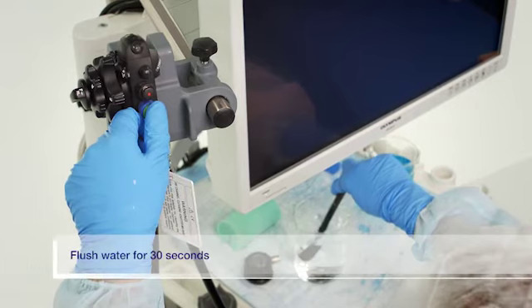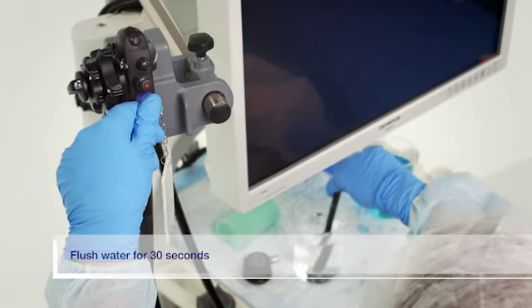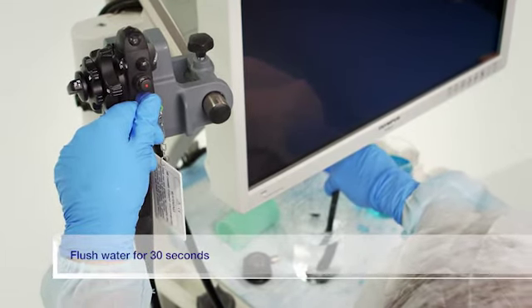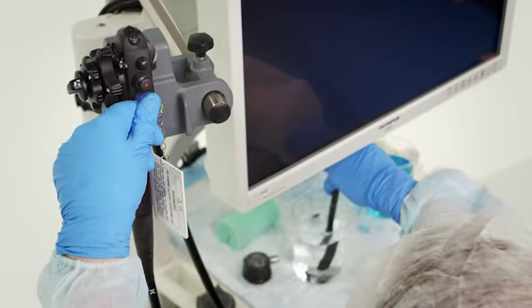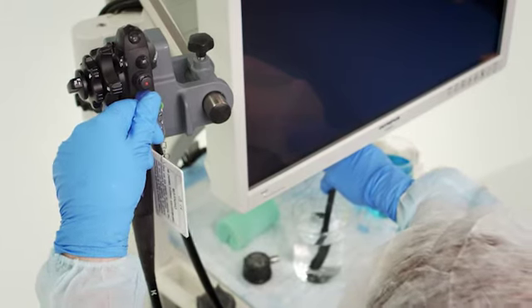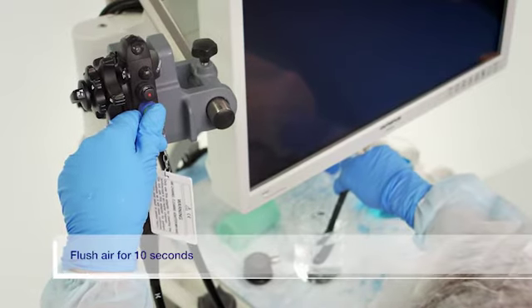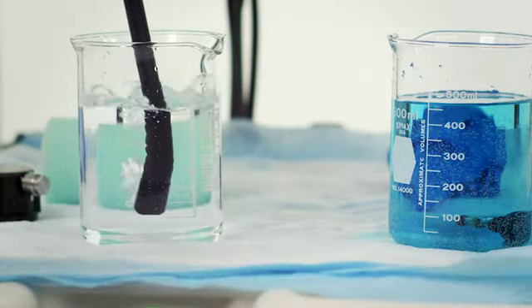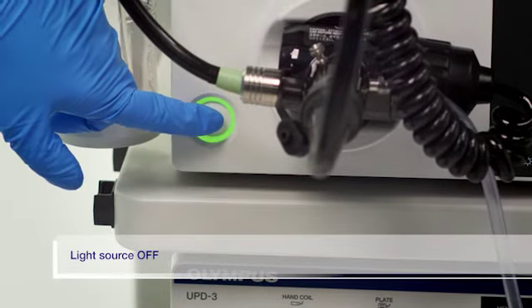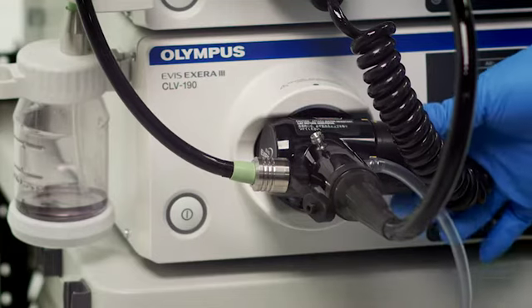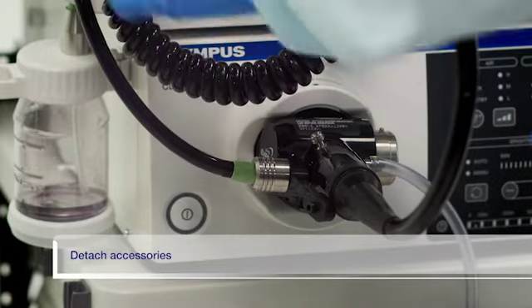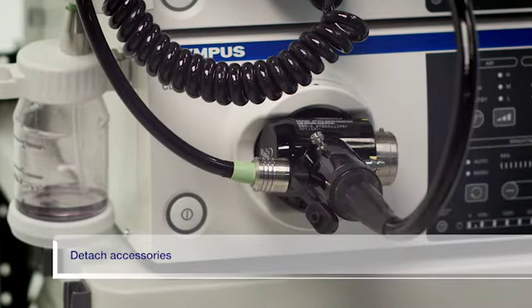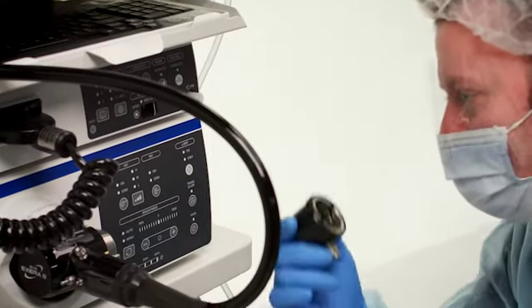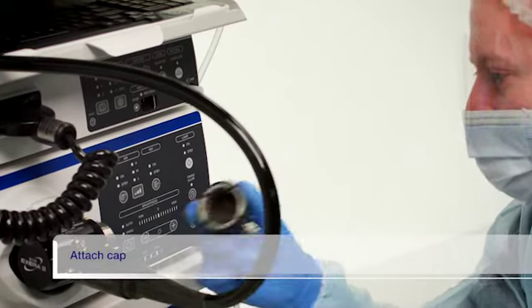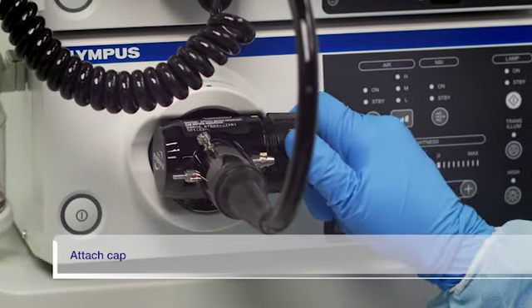Depress the button of the air-water channel cleaning adapter to flush the air-water channel with water from the water container for 30 seconds. Then release the button to flush air for 10 seconds. Turn the light source off. Detach the videoscope cable, suction tube, and water container from the scope. Confirm that the exterior surface of the electrical connector is free from scratches and attach the cap.